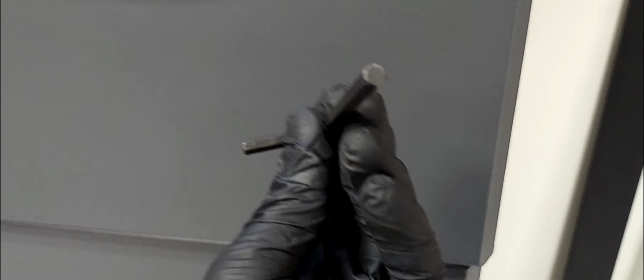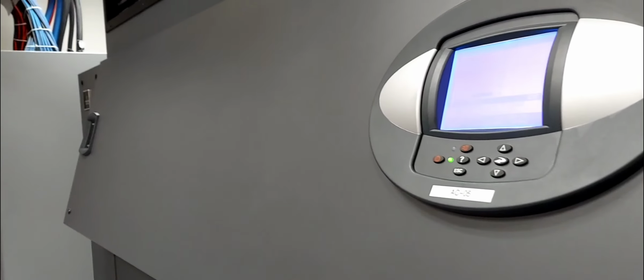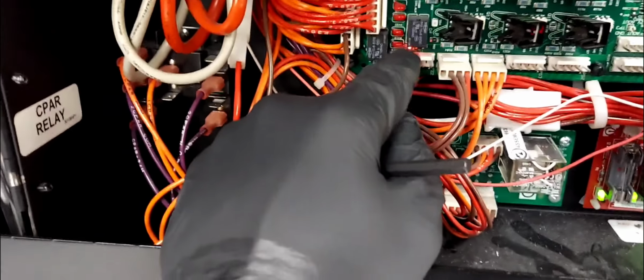So in order to open this unit, you will need a Liebert key or an Allen key like this. See, fits. Alright, also you can see my alarm relay. Yeah, this is the alarm relay right here. And that's on. Alright. So that's the main board in the unit.